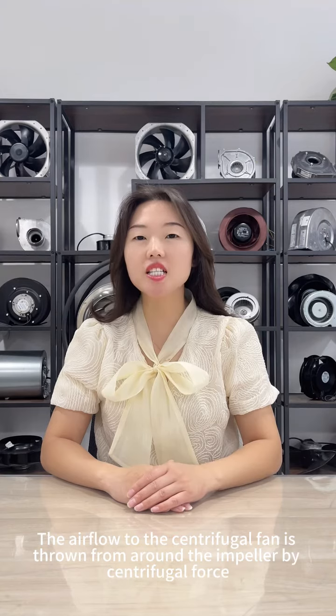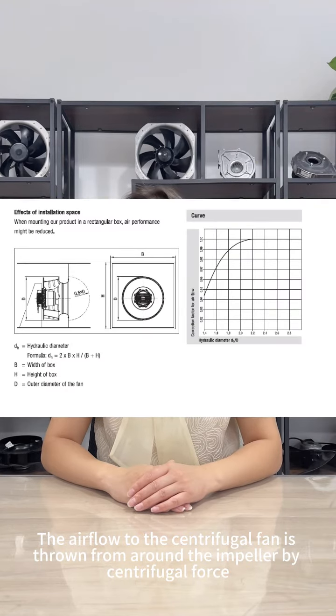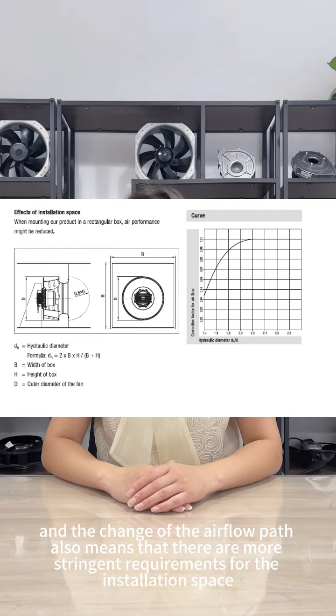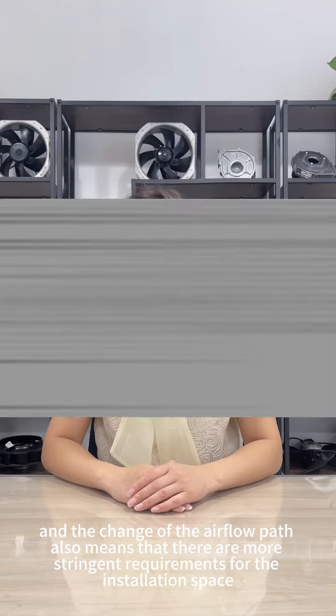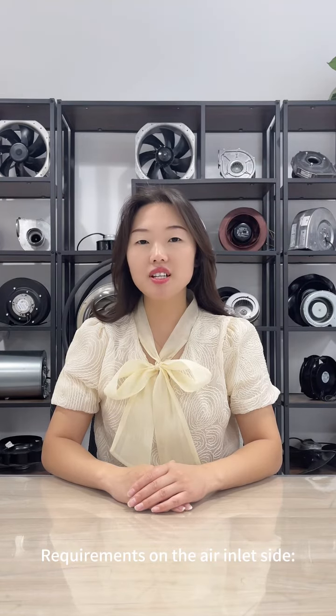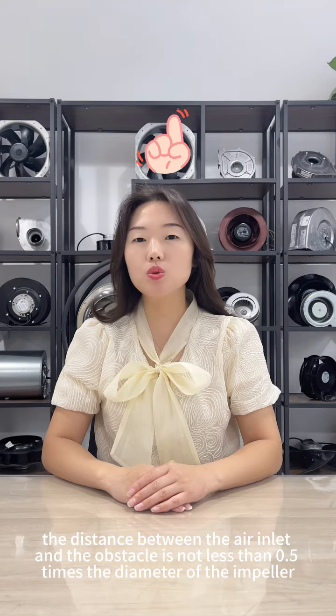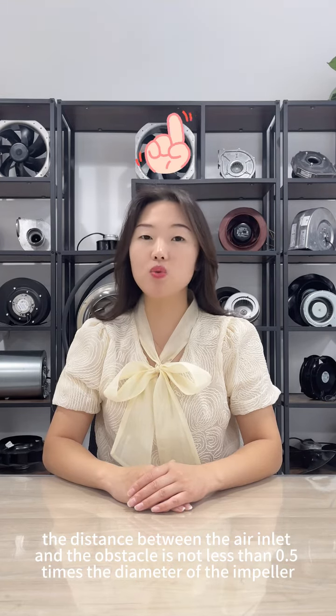The airflow to the centrifugal fan is thrown from around the impeller by centrifugal force, and the change of the airflow path also means that there are more stringent requirements for the installation space. Requirements on the air inlet side: the distance between the air inlet and the obstacle is not less than 0.5 times the diameter of the impeller.